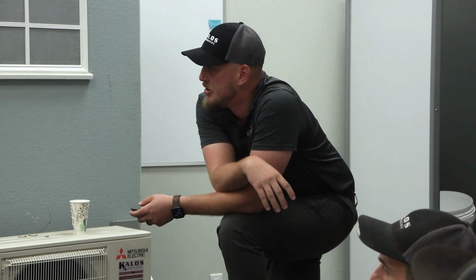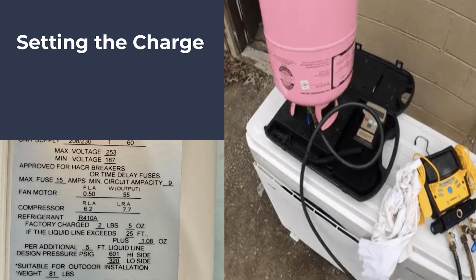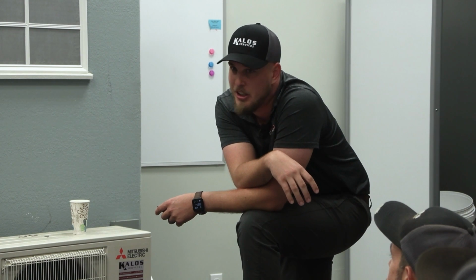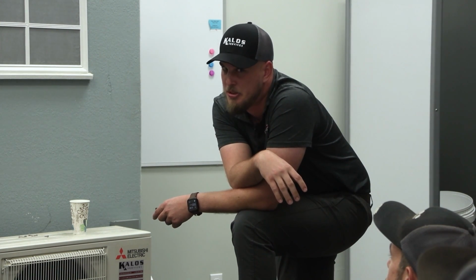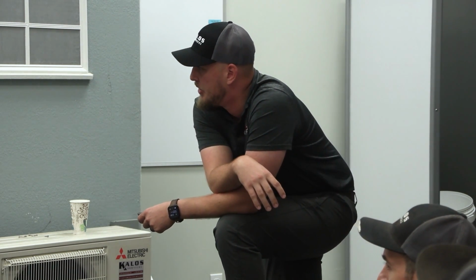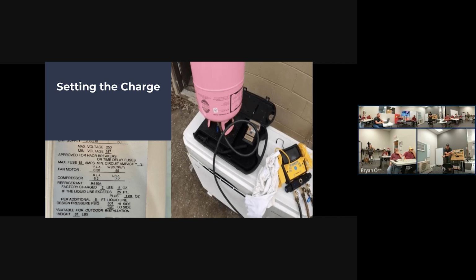And again, a reminder, these units do not hold a lot of refrigerant. This one only holds 2 pounds. So if you find yourself adding over a pound, trying to get your pressures to look good, something's wrong there. So make sure you slow down in this part of the process. Also keep in mind your hoses can hold several ounces of refrigerant. So that alone can impact a critical charge like this. Yeah, with a full tank, your hose can hold like 3 ounces of refrigerant, and then your manifold and maybe your other hose involved in the mix, you could have more than you need just in your hoses.